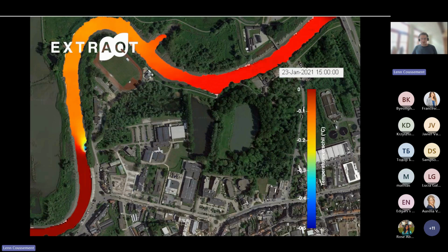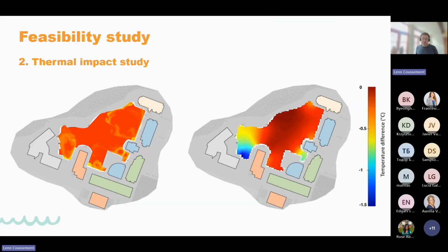So when performing a thermal impact study, you try to calculate these things. On the right you can see a simulation of the temperature differences caused by an open system on a closed water body, where each building has its own system. The building in the corner here is the biggest, which is why you see the darkest color—at this specific moment in the simulation it creates a temperature difference of 1.5 degrees in the water body, which is okay, it's limited.